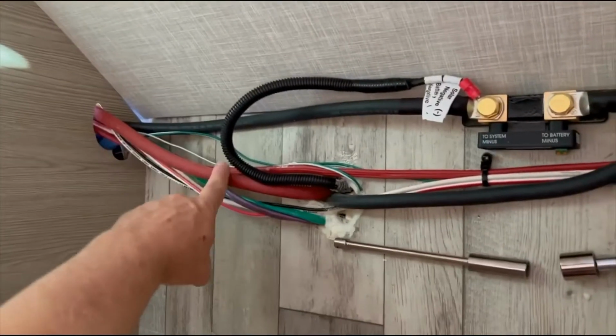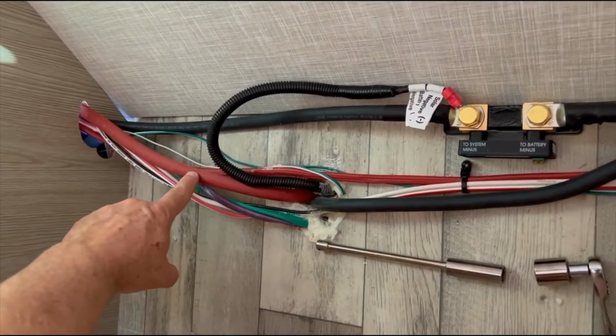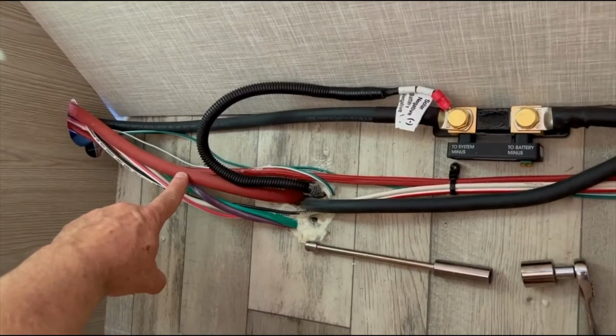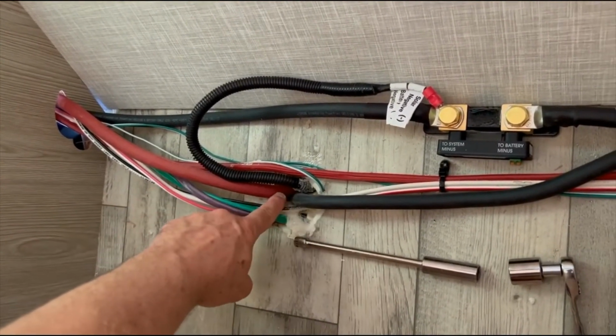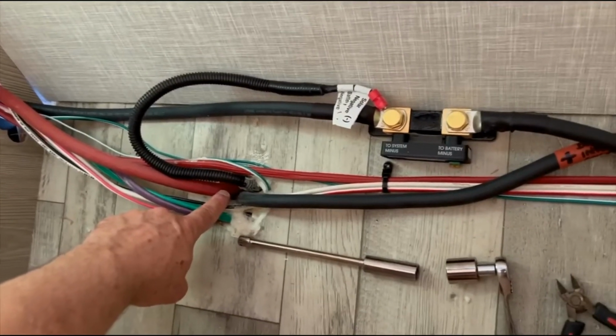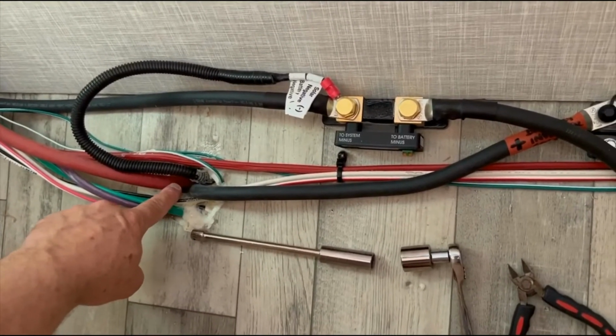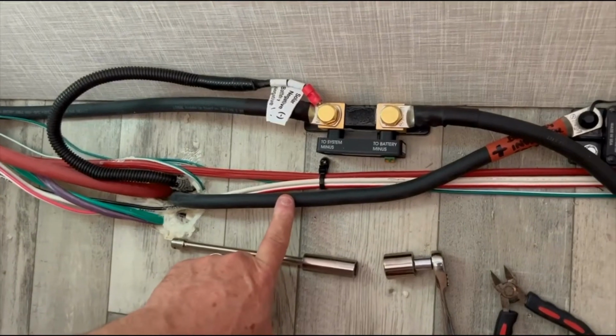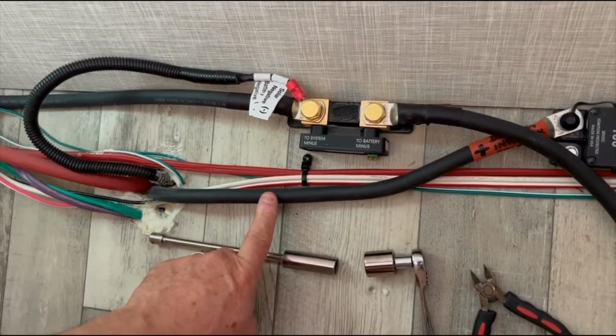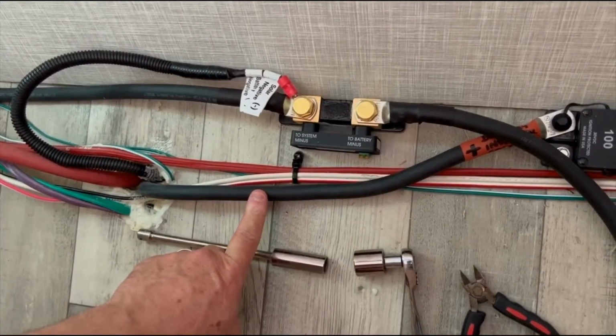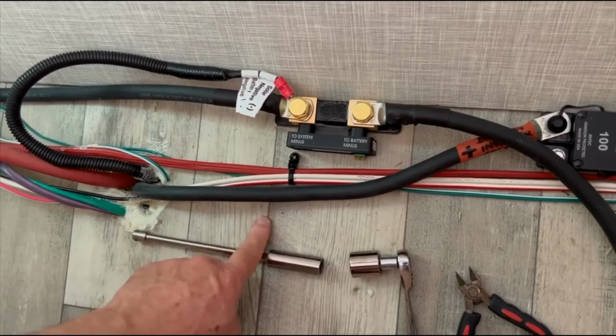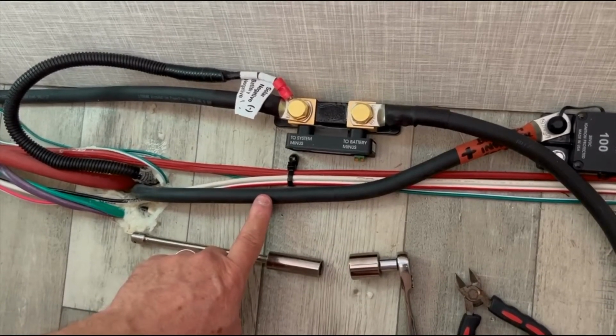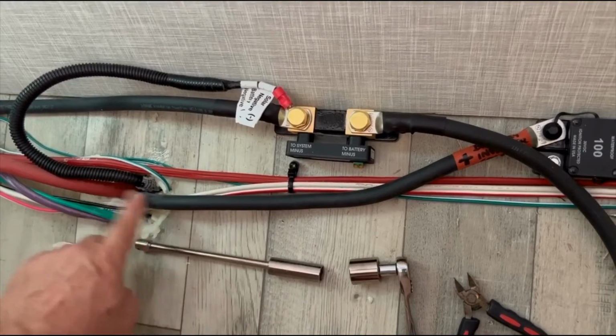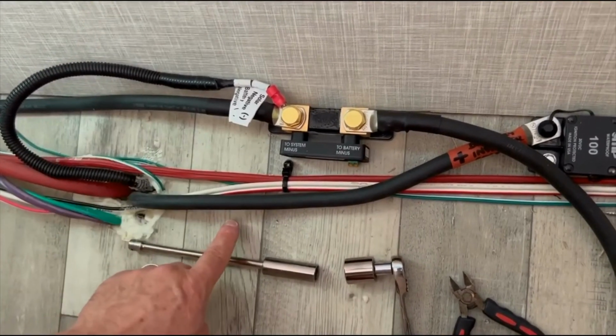All right, here's what we're looking at for wiring on the inside. As you can see, this is the 2-aught gauge cable coming from the inverter. It goes down through the floor and out to the battery disconnect, which I showed you a little bit earlier. Then it comes back as this black cable. Now, I know black cable is normally reserved for the negative side, but I'm using it for the positive side so that I can tell the difference between these two on the outside of the trailer.